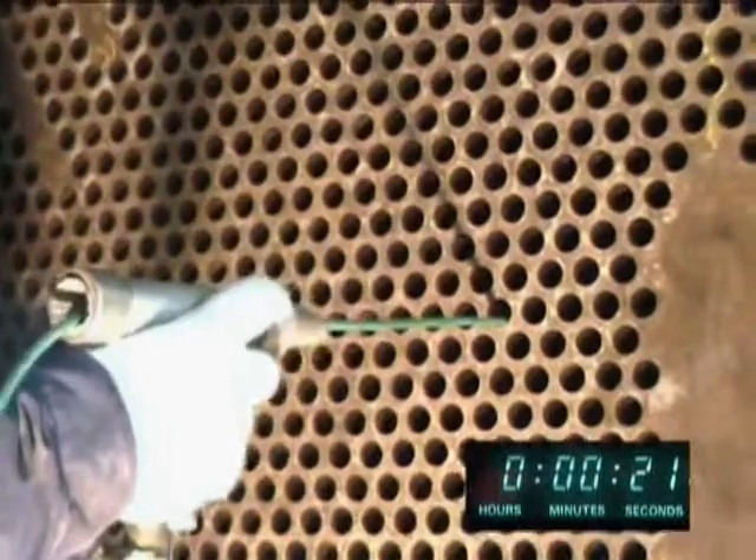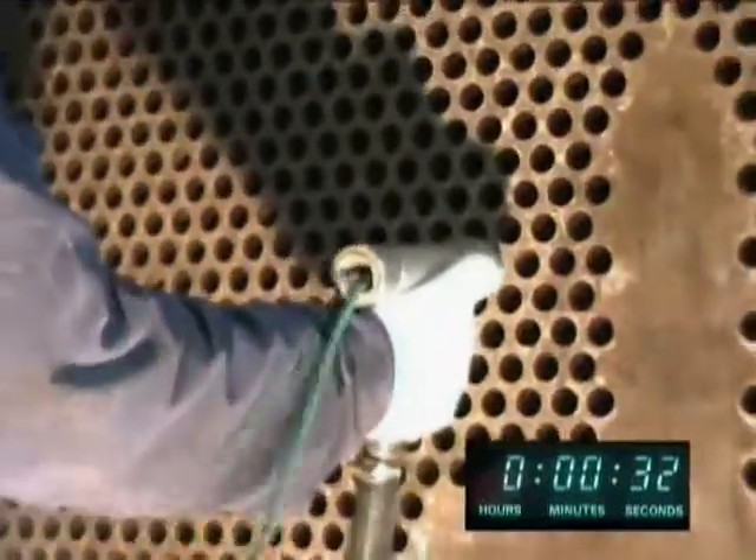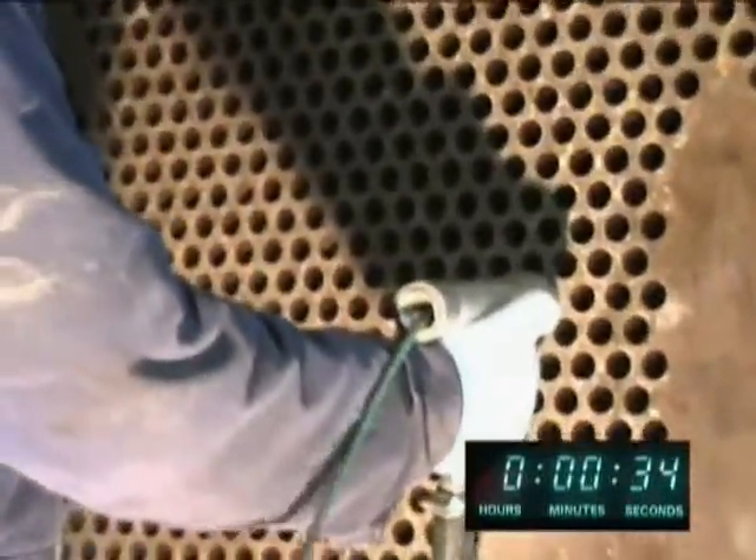As with all eddy current inspections, tube cleaning is strongly recommended, as eddy current probes need a fill factor of 85% or better for optimal results. Even with this ultra-high speed delivery, flaw detection and sizing are not compromised.